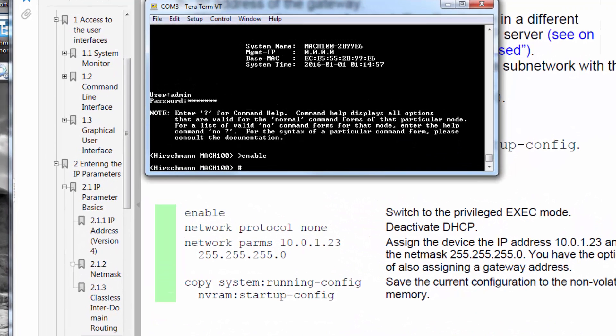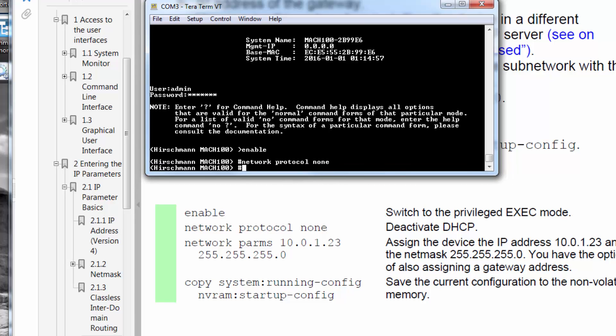Within the manual, you'll also find the appropriate instructions for assigning an IP address. I've already gone in with enable. Next thing I'm going to do is deactivate DHCP, so this is going to be network protocol none. Then I'm going to assign the IP address, network parms 10.10.10.3 with a 24-bit subnet mask.